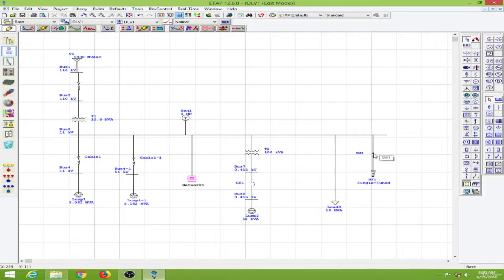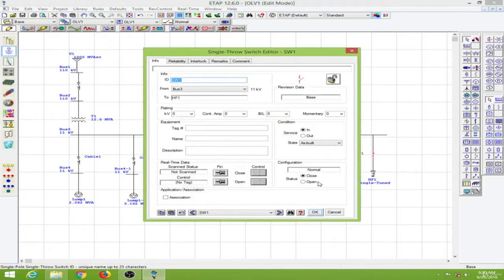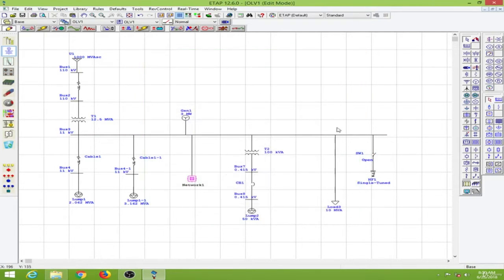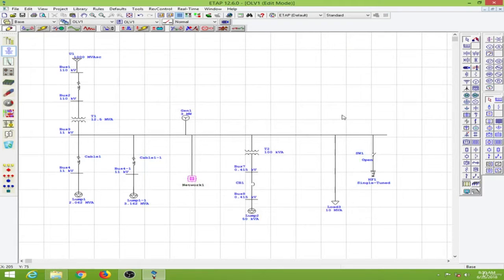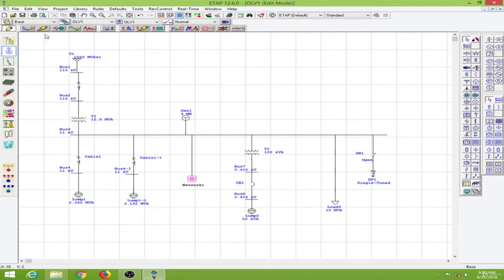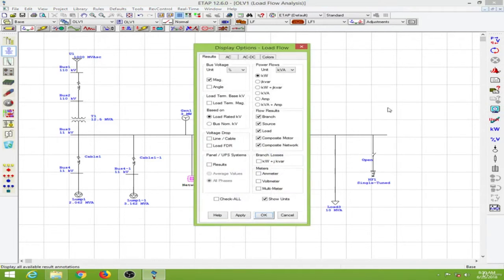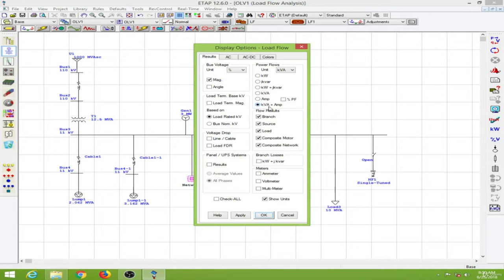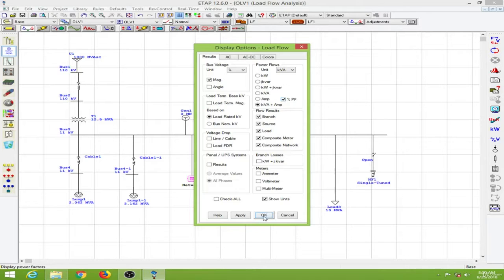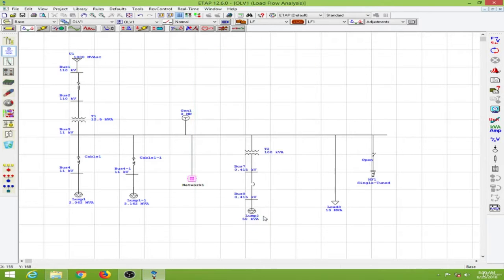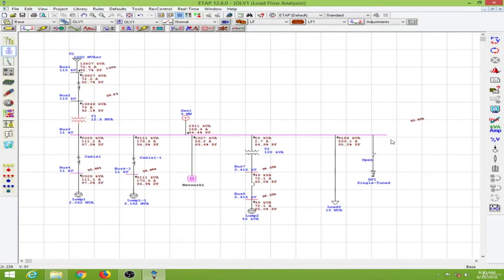I'll open the switch by double clicking and putting it in the open position. To size a harmonic filter we need data from the load flow analysis, so going to the load flow analysis here, I will use the display options to display the kVA plus amp and the percentage power factor. Then conducting the load flow, here we have the data.